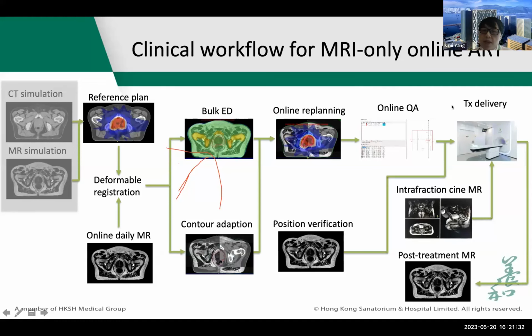And before the final treatment, we also will perform a position verification MR image to make sure that during the whole progress of the online planning, the patient anatomy or the patient position doesn't change just before the beam on. If the patient moves or the anatomy changes, we will initiate another round of the replanning process. And during the treatment delivery, usually we will use the intrafractional cine MR images to observe if the target has moved outside the PTV margin.